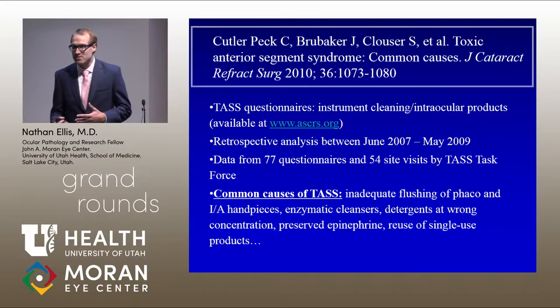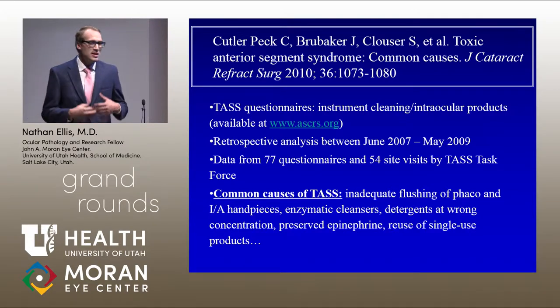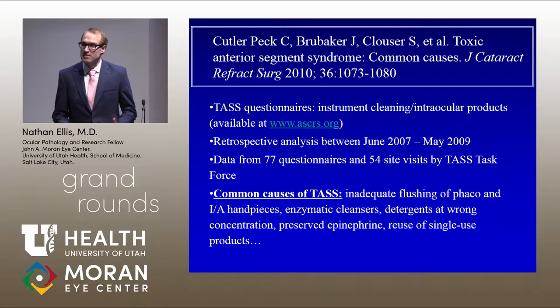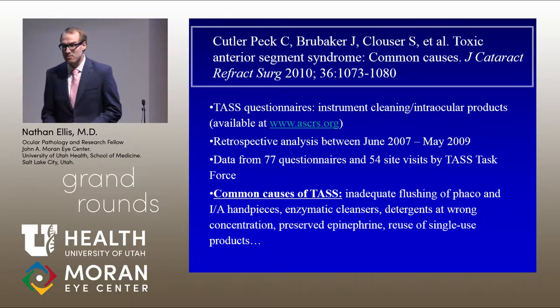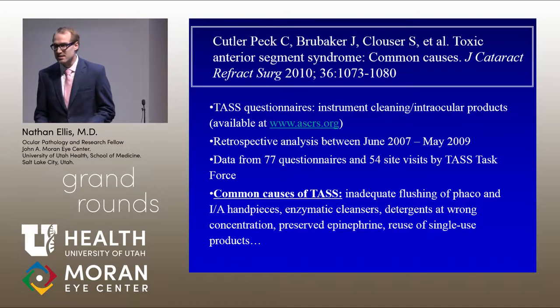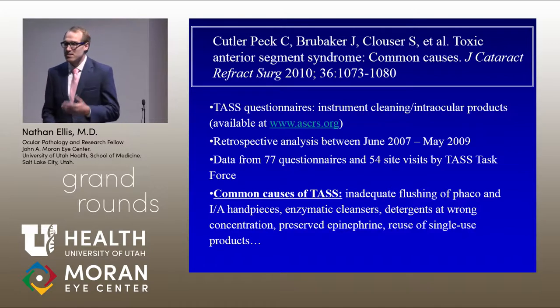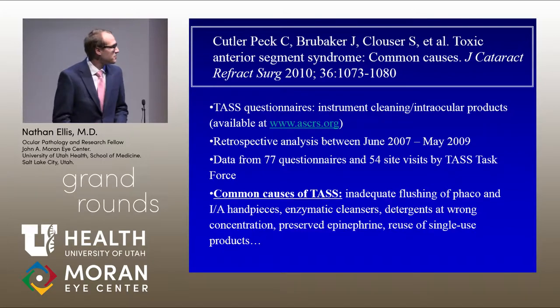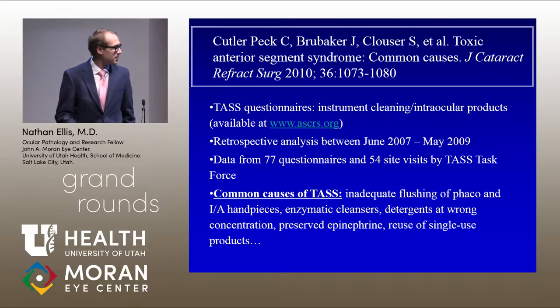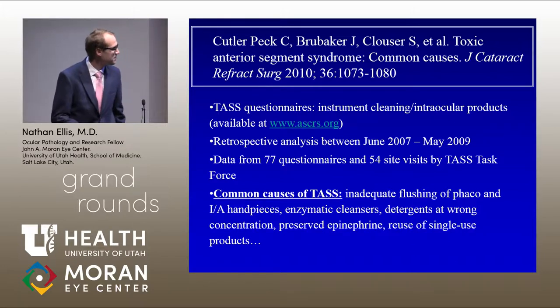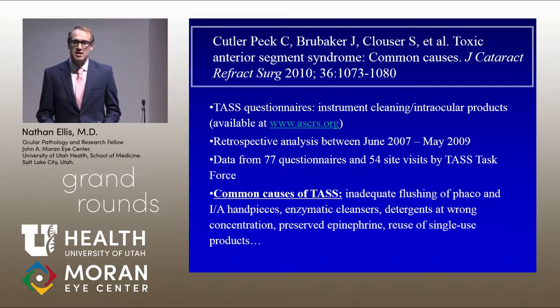The TASS Task Force maintains a questionnaire on the ASCRS website. If a surgery center has an outbreak of TASS, they can fill out the questionnaire regarding their surgical, cleaning, and sterilization techniques. Dr. Mamelis reviews the submissions and makes recommendations to prevent future TASS. In 2010, the first paper examined 77 questionnaires and identified common causes including inadequate flushing of phaco and IA hand pieces, enzymatic cleaners, detergents at wrong concentrations, and preserved epinephrine.